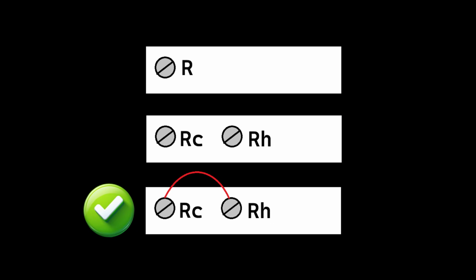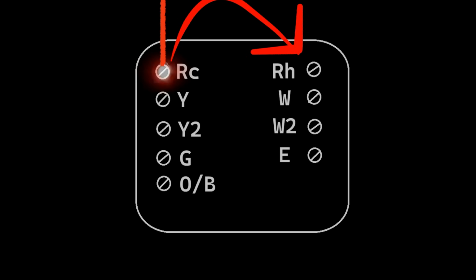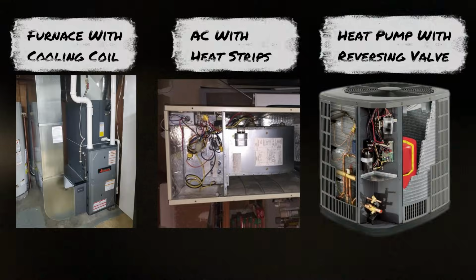When you have a thermostat that has a physical jumper between both of these terminals, what that jumper is doing is telling the thermostat that our heating and cooling are combined into one system and we only have one transformer controlling both, just like our single R terminal that we discussed previously. This will allow the heating terminal to steal 24 volts off of the cooling terminal to activate all the heating terminals associated with it. And this is fine because we are dealing with a single system with a single transformer that does both heating and cooling.